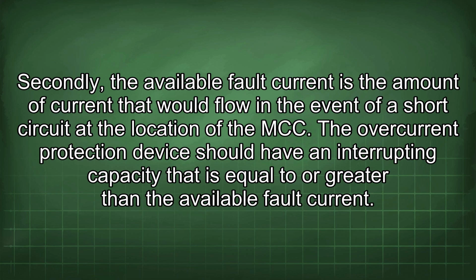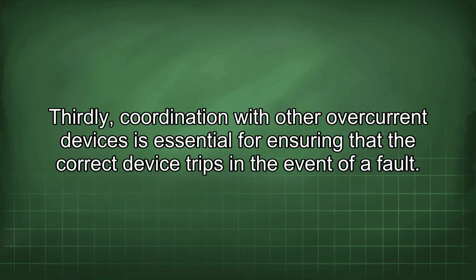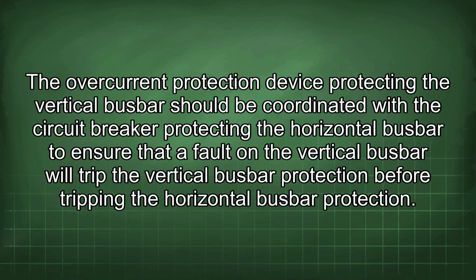Secondly, the available fault current is the amount of current that would flow in the event of a short circuit at the location of the MCC. The overcurrent protection device should have an interrupting capacity that is equal to or greater than the available fault current. Thirdly, coordination with other overcurrent devices is essential for ensuring that the correct device trips in the event of a fault. The overcurrent protection device protecting the vertical busbar should be coordinated with the circuit breaker protecting the horizontal busbar to ensure that a fault on the vertical busbar will trip the vertical busbar protection before tripping the horizontal busbar protection.